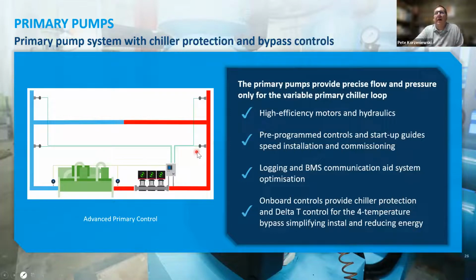Here's a look at a primary pump set in the drawing, blown up a bit. And again, we'll talk about this in a little bit. We've got some differential pressure sensors. We'll add chiller protection, and then we've got the 4 temperature control sensors that we'll need to add across the bypass. We'll talk about operation in a few minutes.